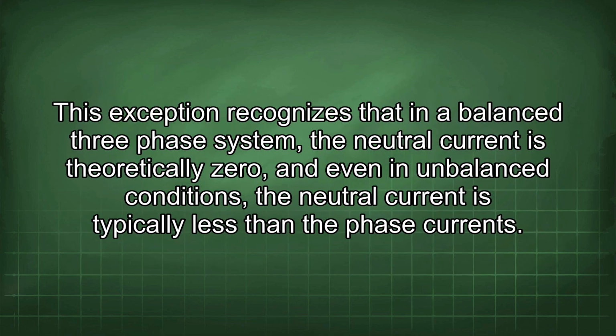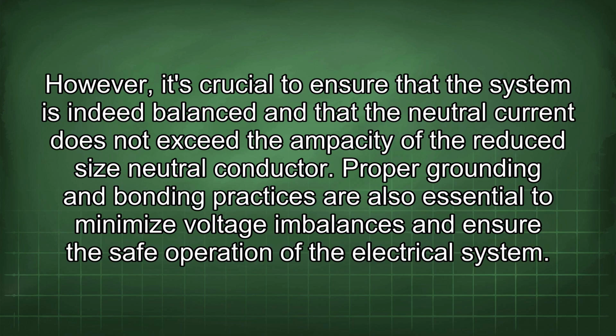This exception recognizes that in a balanced 3-phase system, the neutral current is theoretically zero, and even in unbalanced conditions, the neutral current is typically less than the phase currents. However, it's crucial to ensure that the system is indeed balanced and that the neutral current does not exceed the ampacity of the reduced-size neutral conductor.